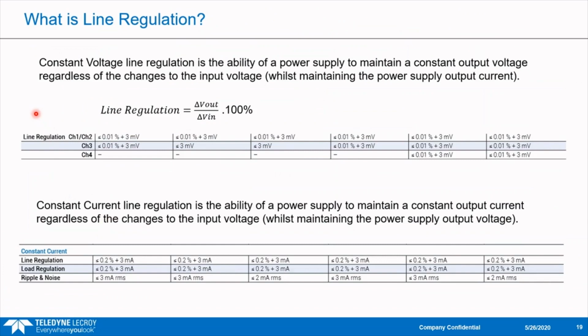So what is line regulation? Constant voltage line regulation, in constant voltage CV mode, is the ability of the power supply to maintain a constant output voltage regardless of changes to the input voltage. We have a formula here: V out over V in as a percentage, and this is the specification for all of those power supplies we were looking at. What you'll notice is they're all pretty much the same, with very little difference between any of them. They're all very, very low levels.